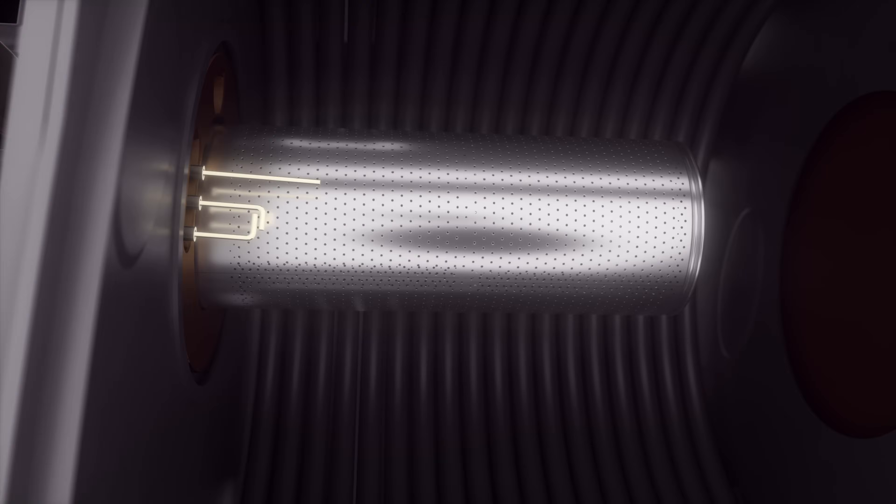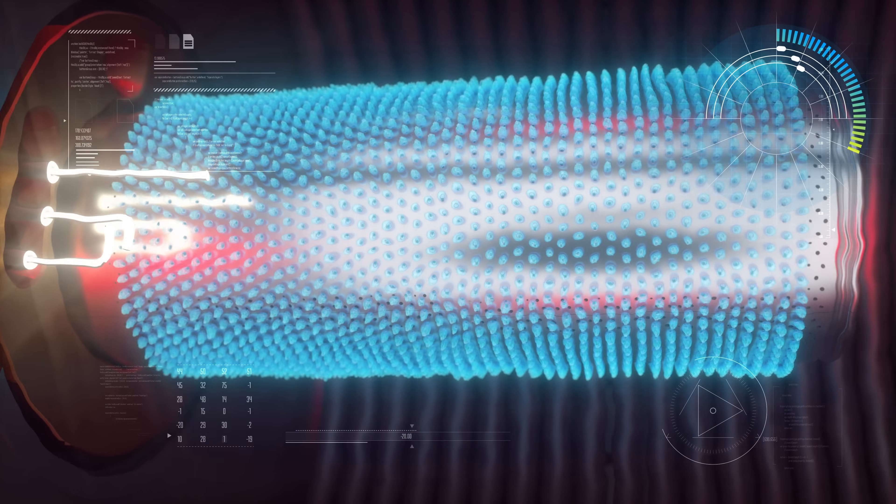With up to a 30 to 1 turndown ratio, the Viessmann modulating matrix cylinder burner meets low NOx requirements and offers the highest water volume in class. No primary boiler pump required.